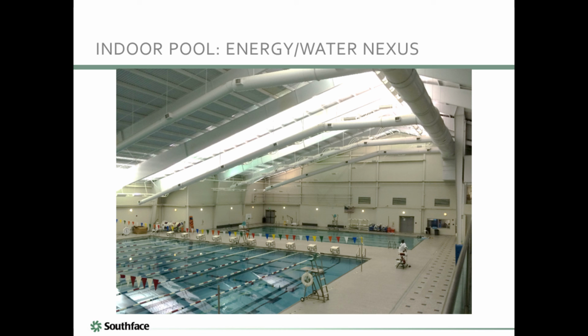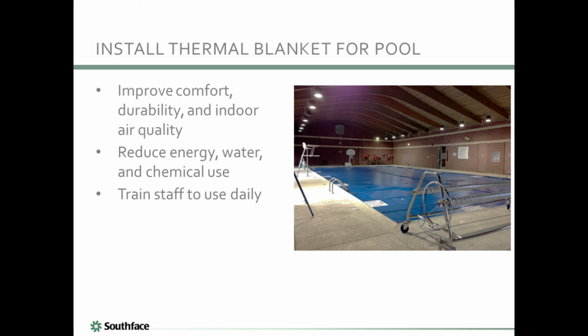The natatorium that was surveyed has 2 pools maintained above 86 degrees with a combined surface area of 8,700 square feet. The air is maintained at about 81 degrees with a relative humidity of 60%. In these conditions, the average evaporative losses are about 50 gallons per hour. And water, whenever it evaporates, absorbs a lot of heat, roughly 8,000 BTUs per gallon. The resulting heat loss to evaporation is around 400,000 BTUs of heat every hour. About 4 therms, although it's not all coming from gas.